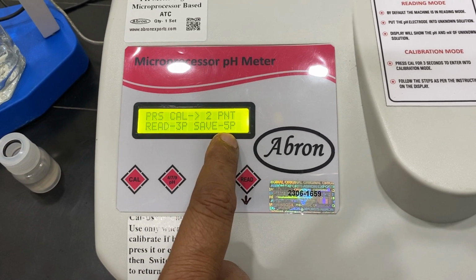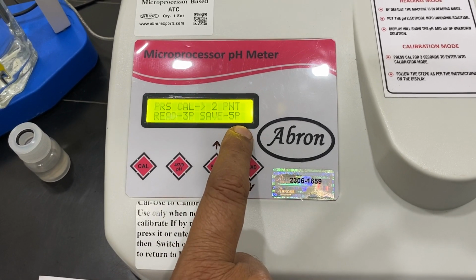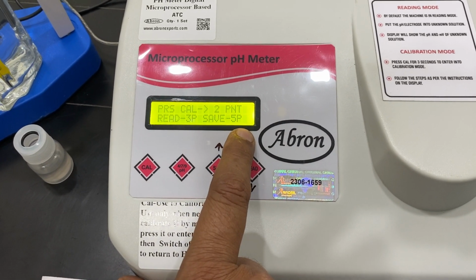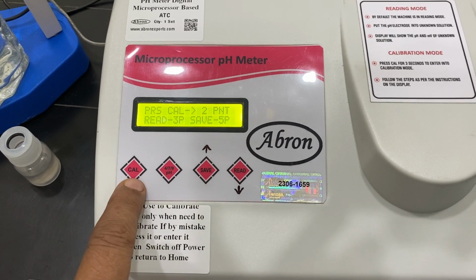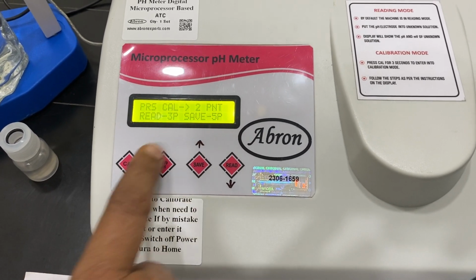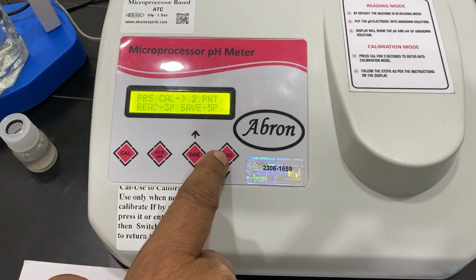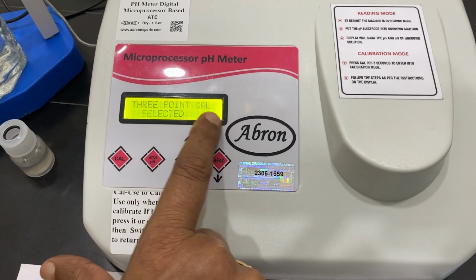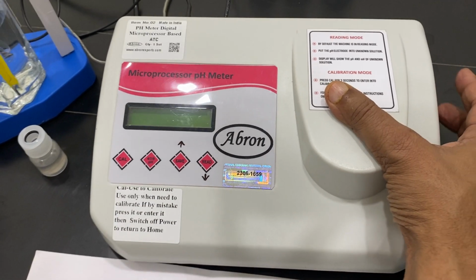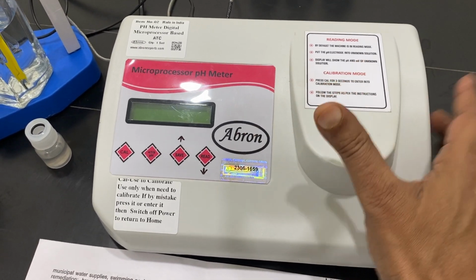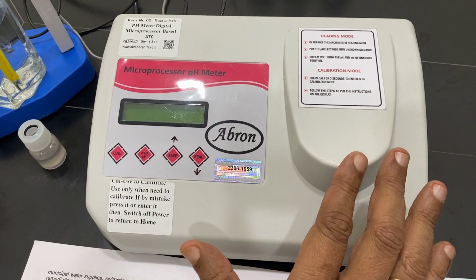There are 5 modes by pressing save, but that is very difficult. Initially, that is required for research. So mostly we suggest you go with the read mode. Read mode means 3-point calibration. And if you have done it, then immediately switch it off if you are not going to calibrate.